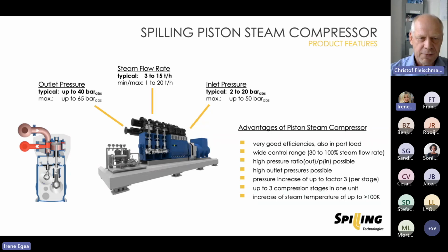What we should have with these piston machines on the inlet side is that the steam entering into the unit is in a certain way pre-compressed. So we say there should be at least around 2 bar absolute, 1 bar gauge. Otherwise, the mass flow, what we can handle with these units, is comparatively low when the steam pressure is even lower at the inlet. And so the machines also become relatively expensive. So it's an economical point of view that there should be these 2 bar at the inlet about.